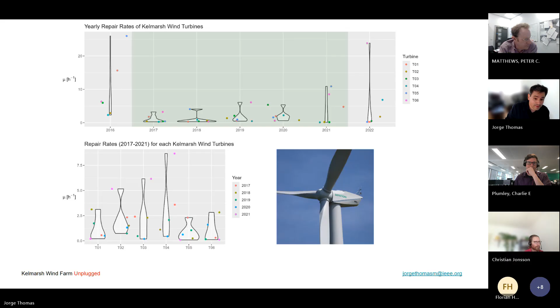Let's talk about a quick stop in Monte Carlo, more than 1,000 years of service. Once I have the parameters of the distributions for failures and repair rates, I can start sampling, generating random numbers representing the duration of these events. What I'm looking for is the forced outage rate, the unavailability hours per year, on the long run.